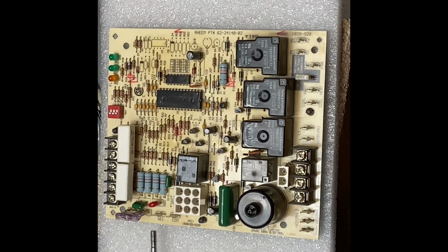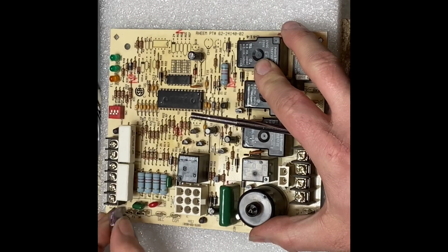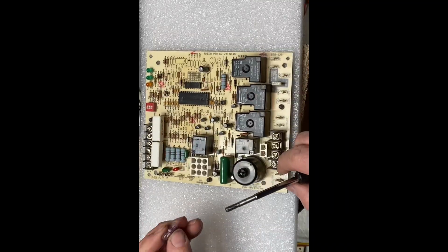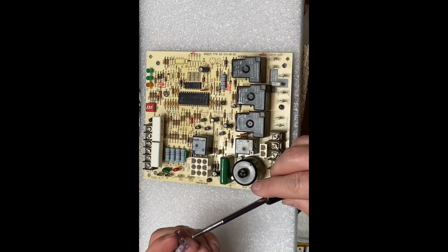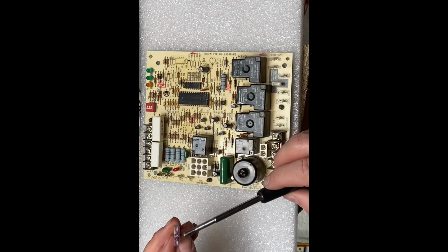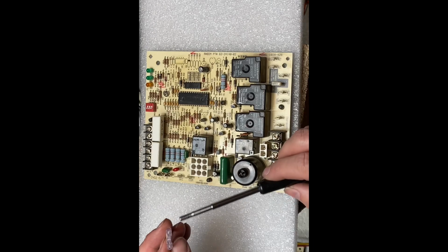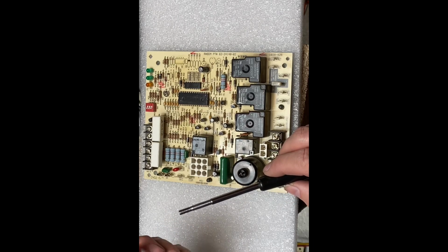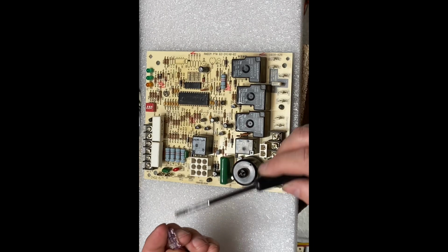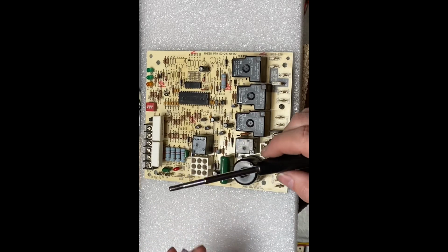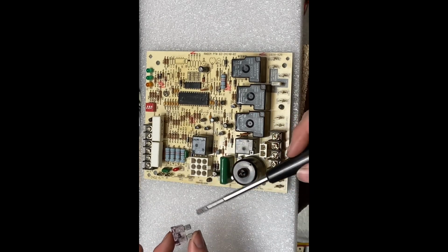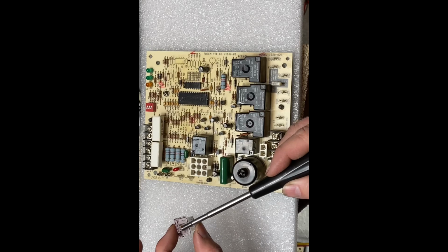From there, it immediately goes into our fuse. And what's nice about this, the fuse is mounted straight into the control board, and it's going to be either a 3 amp fuse like this or a 6 amp fuse. Don't get this confused for a letter. It is a 3, which is a number, and a 6, which is a number. Sometimes people look at these upside down and think it's an E or a 6, and that gets really confusing when you go to the supply house.